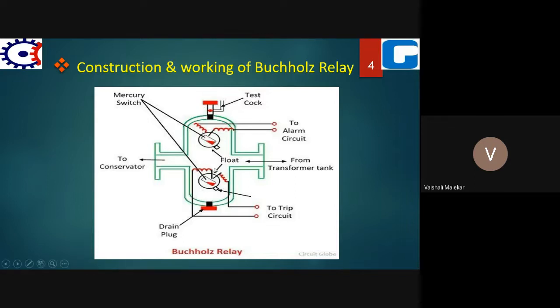On the top side, you can see a hinged float accompanied with a mercury switch, and the mercury switch is connected with the alarm circuit. Similarly, on the lower side, you can see the hinge float. It is also accompanied with a mercury switch, and this mercury switch is connected to the external trip circuit. The mercury switch here is used for actuating the tripping circuit.